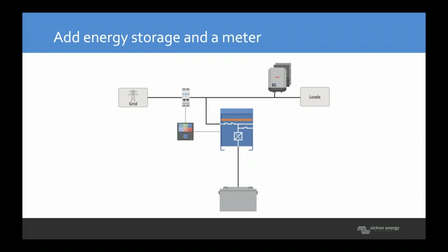If you include a Victron inverter charger with a battery and a grid meter, you begin to use that existing bus of the grid and the loads in the AC PV inverter, and you can now efficiently use that system to charge a battery. So during the day, when there's surplus power from the panels, that can be used to charge a battery. And then at night, when there's a deficiency in the solar but extra load, the battery can discharge through the Victron inverter charger, and that can then provide for the loads at nighttime, meaning the grid power is reduced.